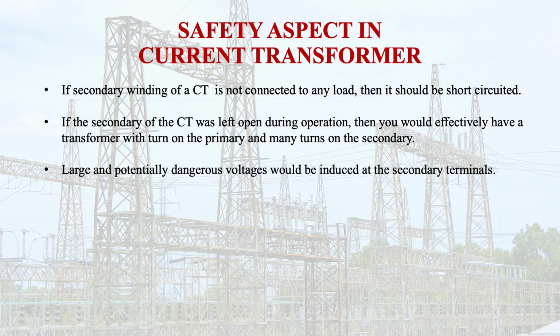So large and potentially dangerous voltages would be induced at the secondary terminal. So if the secondary of the CT is not connected to any load, it should be short circuited.